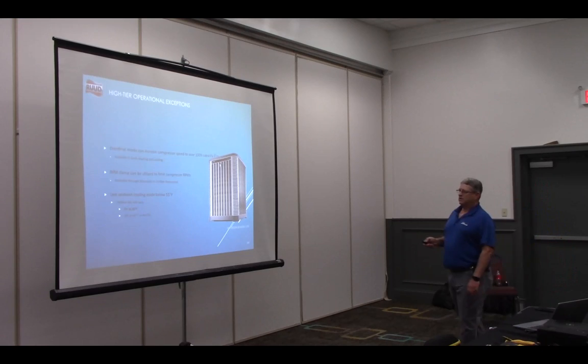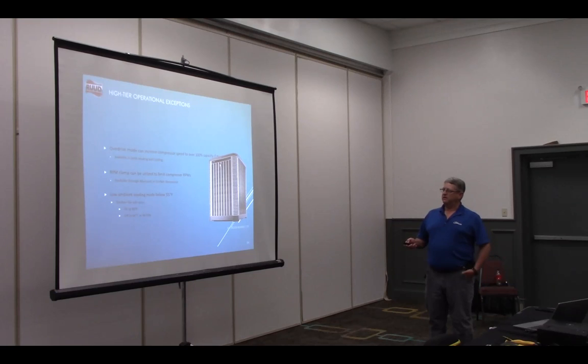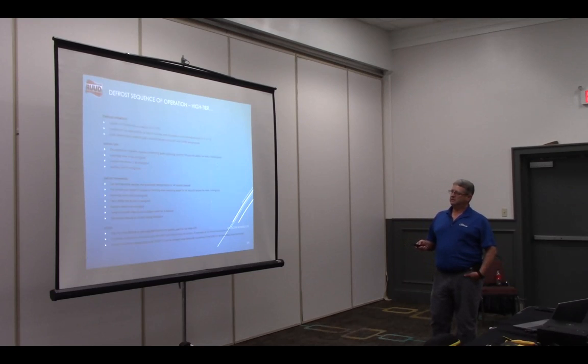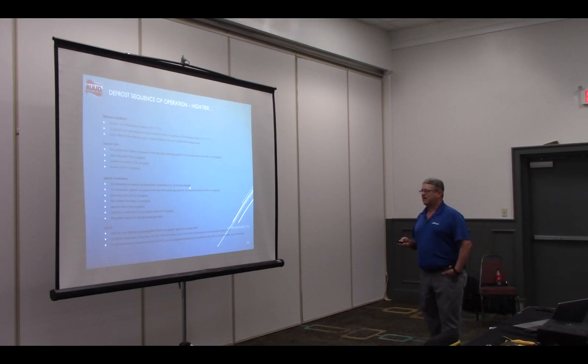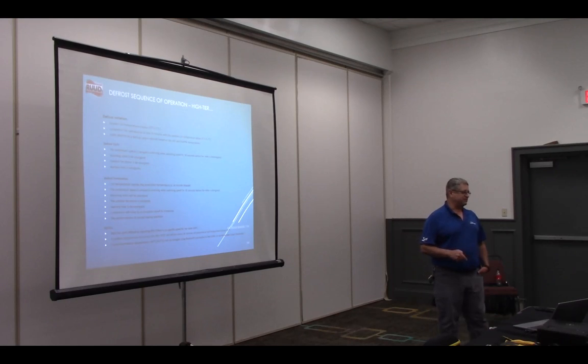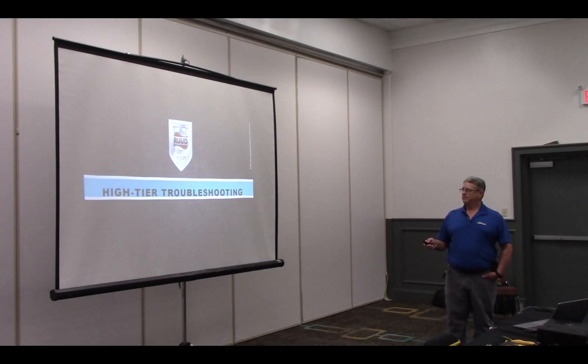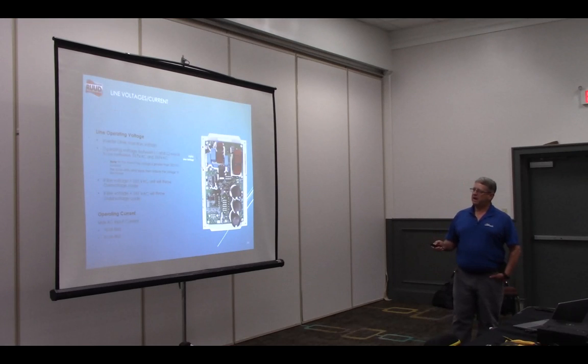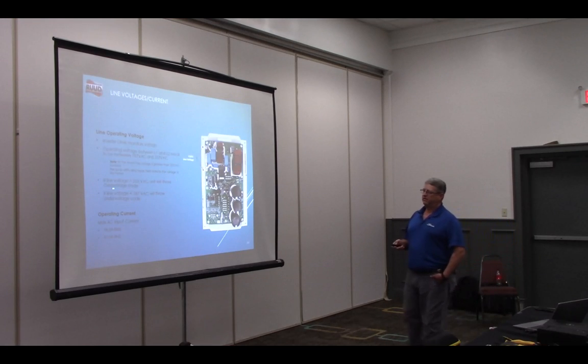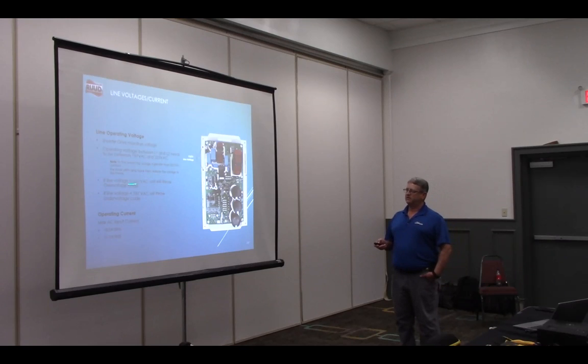We talked about our low ambient cooling outside. We talked about our defrost initiation in our high temp. It's the same for the mid-tier, high-tier. It's all the same sequence, and you can put it in manual defrost by holding that test button down for 5 seconds. Okay. And our high-tier troubleshooting, same voltages here between 197 and 253. At 265 it throws an alarm, and at 187 it throws an alarm.